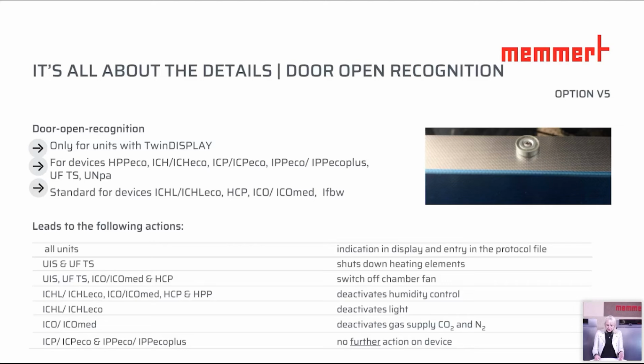This leads to the following actions. If we have ovens, it will shut down the heating element when the door is open. If we have units with blowers, the blower is switched off. If it's for humidity units, then it also deactivates humidity control, so there will not come humidity in the chamber anymore. For the ICHL, ICHLeco, where this is also standard execution, the light is going to be switched off whenever the door is open. For ICO, ICOmed, it deactivates gas supply, CO2 and N2. And ICP, ICPeco, IPPeco, IPPecoplus, no further action on the device.